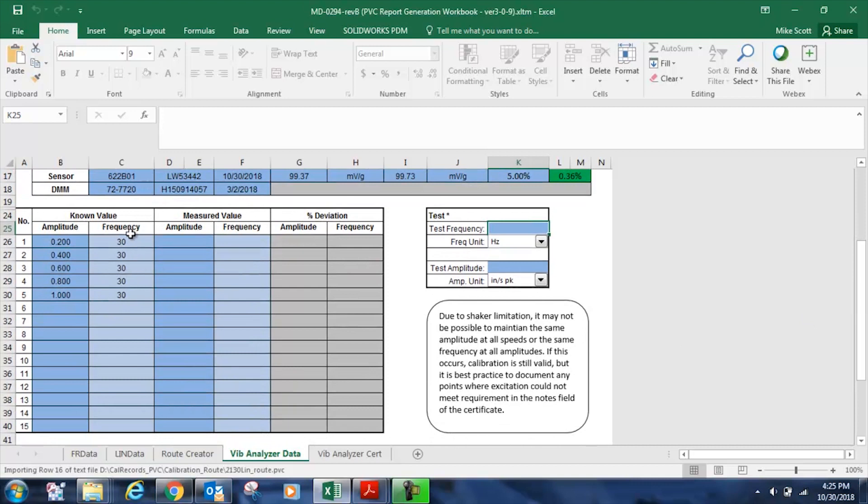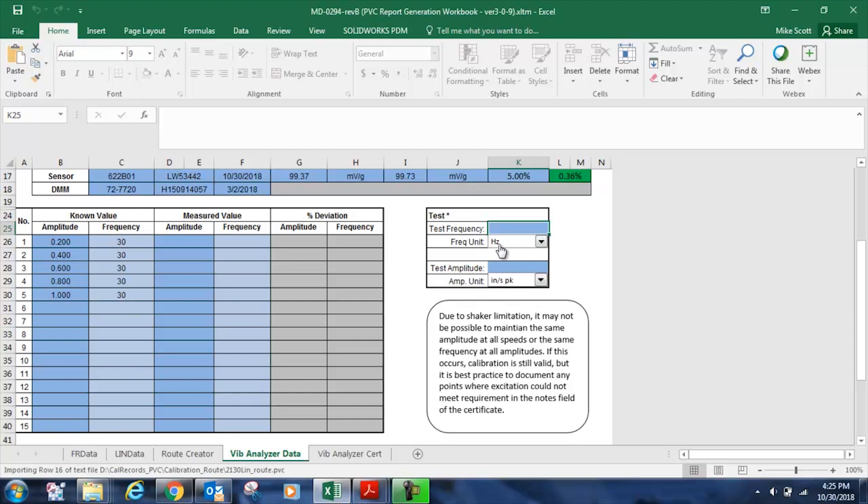into the document, and it warns me to make sure that the frequency or the amplitude units are the same for all test points. In this case, I'm doing a linearity certificate, so the frequency units are all going to be the same. And now that I've imported the test, this is the same test that you saw me use in the video, with my known amplitudes of 0.2, 0.4, 0.6, 0.8, and 1 inch per second peak. And that scale factor has been uploaded here automatically, and the frequency unit in hertz at the 30 hertz frequency.